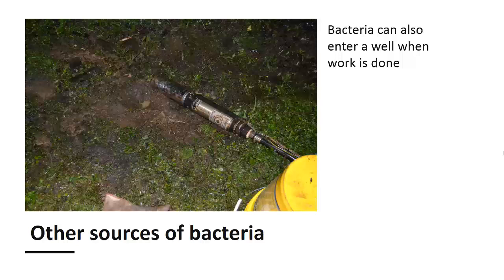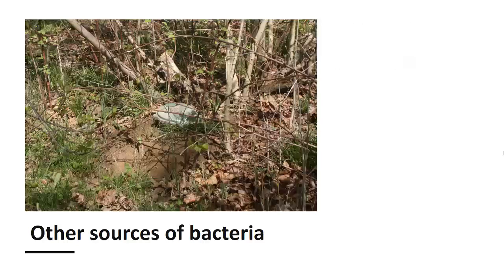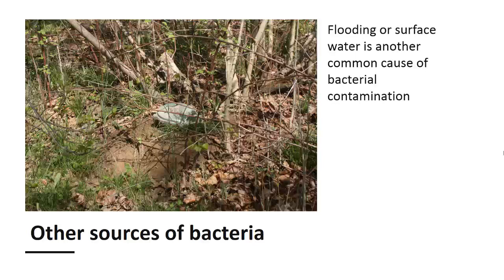Anytime work is done to the well, it should be disinfected with a shock chlorination process, which is described later in this video. Flooding or surface water is another common cause for bacterial contamination of wells. This picture shows a well in a flood plain where surface water can easily enter the well. Anytime your well becomes flooded or muddy after a rainstorm, it will need to be disinfected to remove bacteria that almost certainly came with the high water.